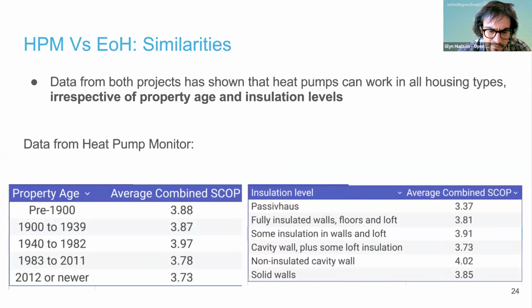Another similarity between what we've seen on HeatPumpMonitor and electrification of heat data is that heat pumps can work in houses irrespective of the property age and insulation level. We pulled the data from HeatPumpMonitor to look at this in detail, and you can see the table on the left here, a range of different ages of properties, and there wasn't a significant difference in the performance of the heat pumps in those different properties. And the same on the right, we've got a table here showing different levels of insulation in houses, and again the SCOP performance didn't differ considerably with different amounts of insulation. So I think once you've got loft insulation and good fit in doors and windows, putting a heat pump in should definitely be the next thing on the agenda.